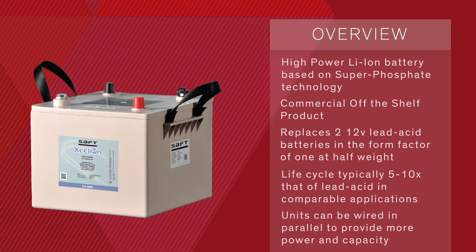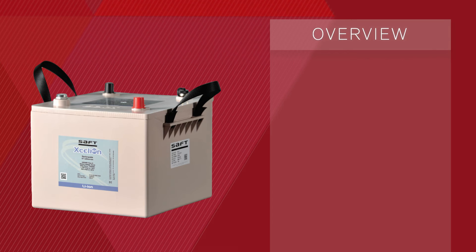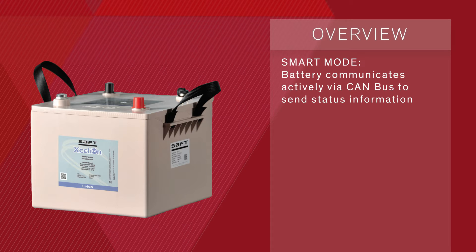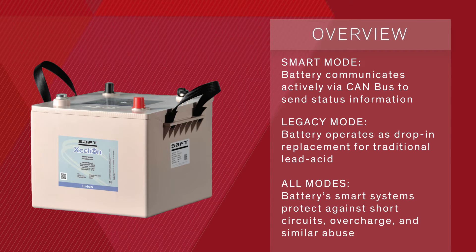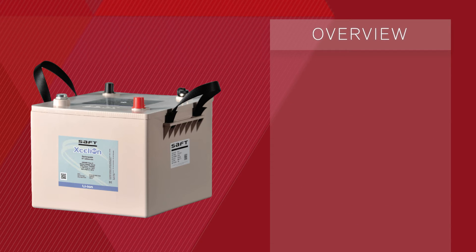Units can be wired in parallel to provide more power and capacity. The Xcelion 6T has two operating modes. In smart mode, the battery communicates actively via a CAN bus to send status information including state of charge, state of health, and diagnostics information. In legacy mode, the battery operates as a drop-in replacement for traditional lead-acid battery without communications or control.